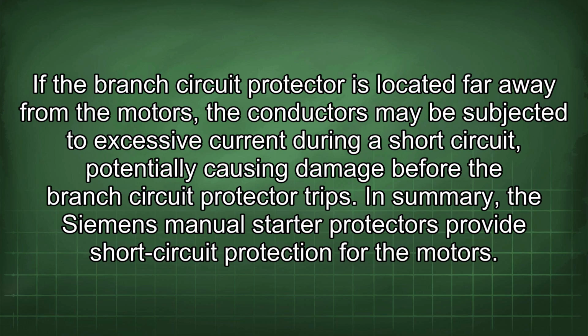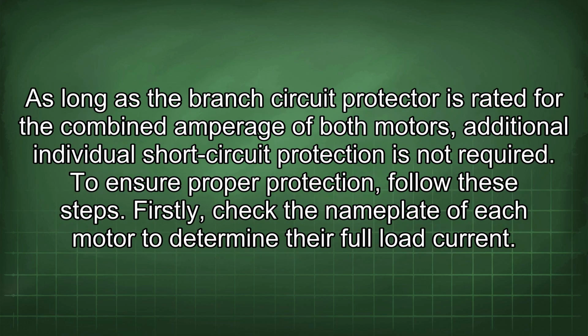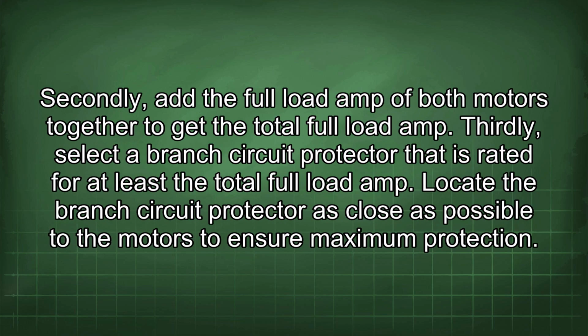In summary, the Siemens manual starter protectors provide short circuit protection for the motors. As long as the branch circuit protector is rated for the combined amperage of both motors, additional individual short circuit protection is not required. To ensure proper protection, follow these steps. Firstly, check the nameplate of each motor to determine their full load current. Secondly, add the full load amp of both motors together to get the total full load amp. Thirdly, select a branch circuit protector that is rated for at least the total full load amp.